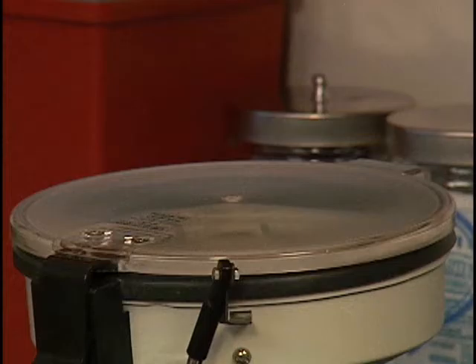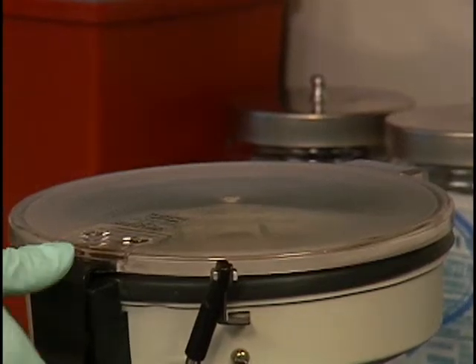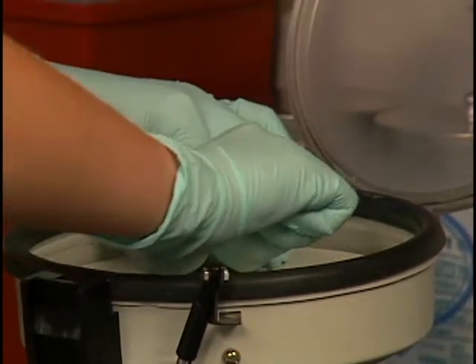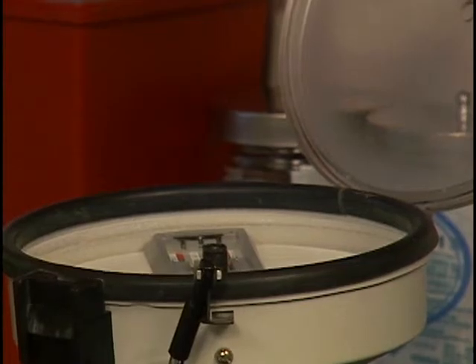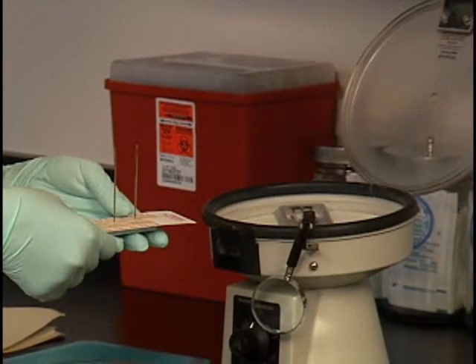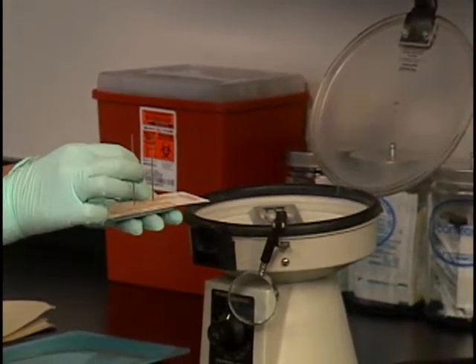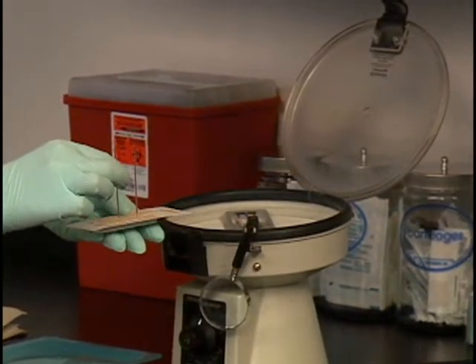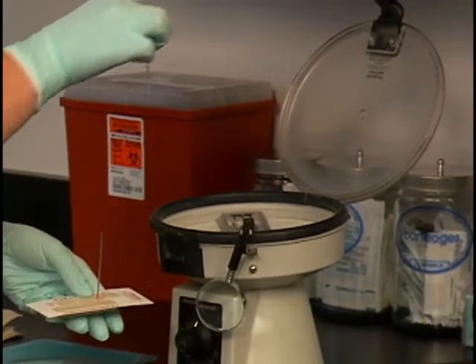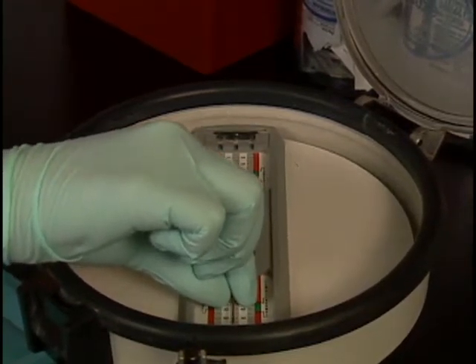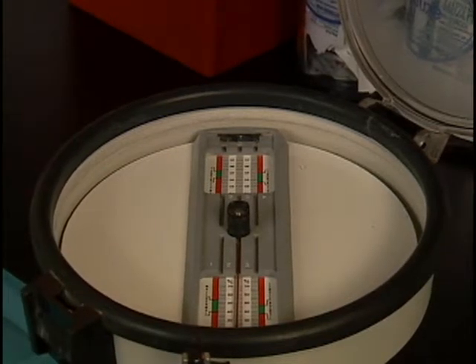Now you must centrifuge the capillary tubes in a microhematocrit centrifuge. Open the centrifuge and unlock and remove the protective capillary tube cover. Pick up the sealing compound holder. Before removing a capillary tube from the sealing compound, rotate the tube between your thumb and index finger. This prevents the sealing compound from pulling out when the tube is lifted out of the sealing compound. Place the capillary tube in the centrifuge with the sealed end facing out. This prevents blood from spinning out during centrifugation.